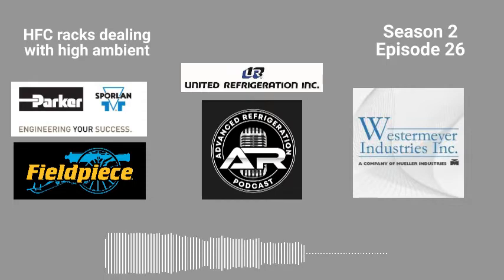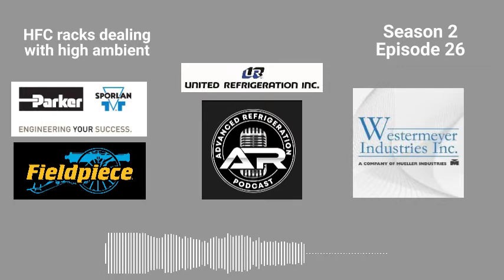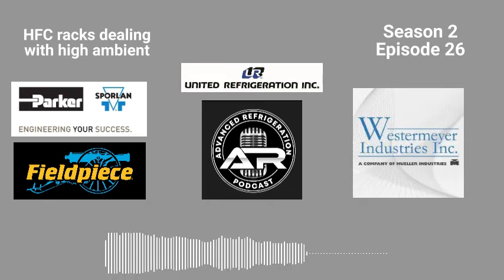Well, yeah, and you got to watch the roofs too. But if you got to remember, a lot of these stores, their condensers aren't by exhaust fans. They're not getting greasy like a normal store would, so they don't get cleaned with chemical like that often. I cleaned one this week that I'd cleaned with water like 3 times, and it was coming out halfway decent. I poured an acid on that thing, let it sit for half an hour with the rack off, and started power washing it again.